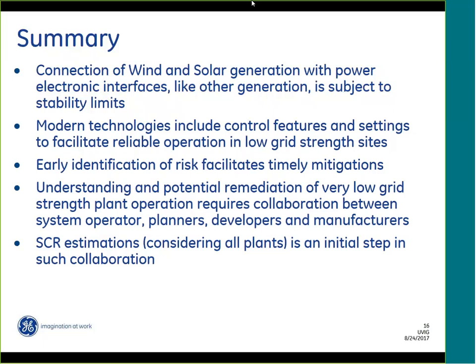The reactive power, the fast reactive power control capabilities, and the active power reduction options that wind turbines have these days can be very effective in mitigating stability issues related to faults in the AC system on the other end of the HVDC or in the DC system. Overall, I think there is very good compatibility. It's possible to operate those systems with short-circuit ratios quite low, lower than the numbers I mentioned, if the wind turbines or solar plants are connected on the rectifier end of the system, which is typically what is intended anyway, and if these converters have the features becoming more and more frequent in the industry.